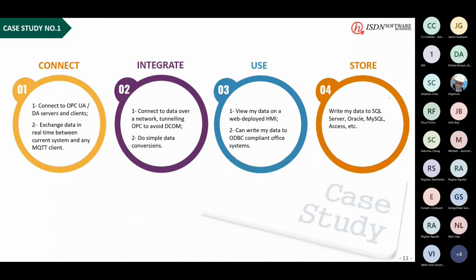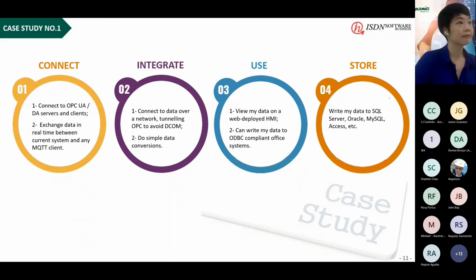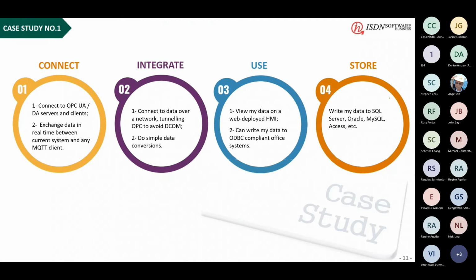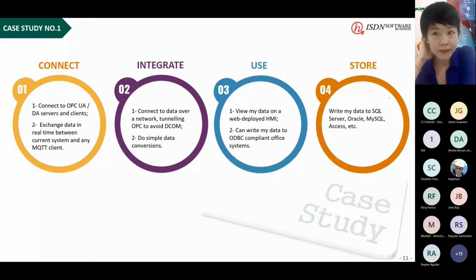First, they want to connect OPC UA and DA data from server to client. Next, they also need to exchange data in real time between their current system and any MQTT client. For integration, they want to connect to a network and avoid DCOM, as we discussed earlier, so it eliminates the DCOM. Using Cogent DataHub avoids the DCOM configuration and allows simple data conversion.